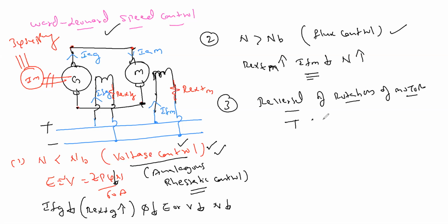टॉर्क को रिवर्स करना, torque is proportional to phi Ia. So now what I can do, by reversing the excitation of the motor, देखा इधर, flux can be minus, or you can see here now, minus phi Ia, or you can have phi minus Ia. Anything you can do. So then speed will be reversed. The rotation opposite में आ जाएगा, क्योंकि टॉर्क opposite में आ रहा है. ये कैसे कर सकते हैं? फ्लक्स को opposite by interchanging the motor excitation.